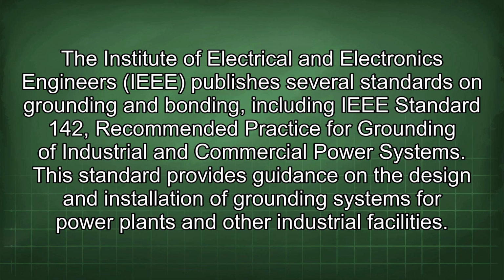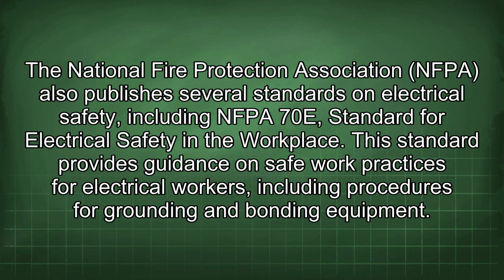The Institute of Electrical and Electronics Engineers (IEEE) publishes several standards on grounding and bonding, including IEEE Standard 142, Recommended Practice for Grounding of Industrial and Commercial Power Systems. This standard provides guidance on the design and installation of grounding systems for power plants and other industrial facilities. The National Fire Protection Association (NFPA) also publishes several standards on electrical safety, including NFPA 70E, Standard for Electrical Safety in the Workplace. This standard provides guidance on safe work practices for electrical workers, including procedures for grounding and bonding equipment.